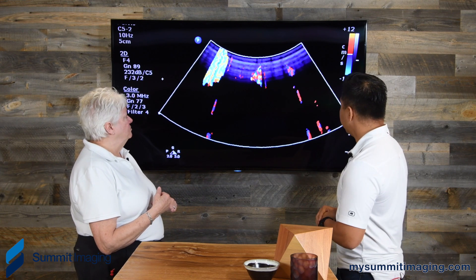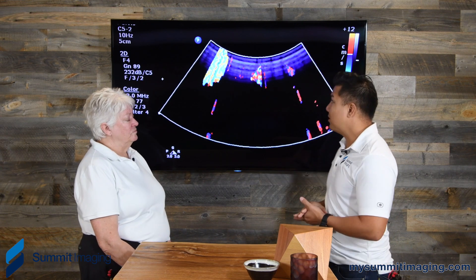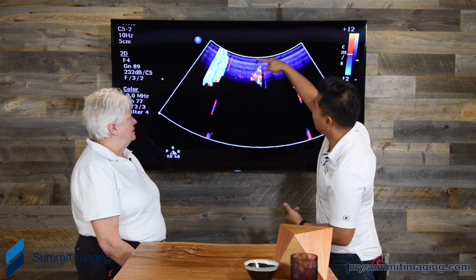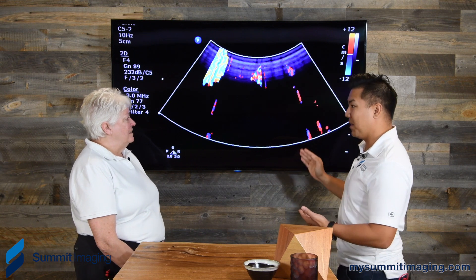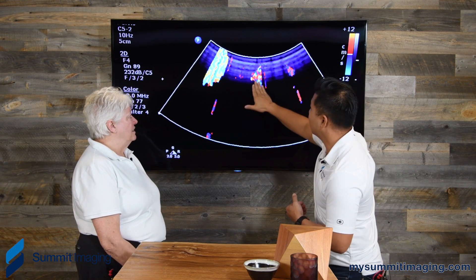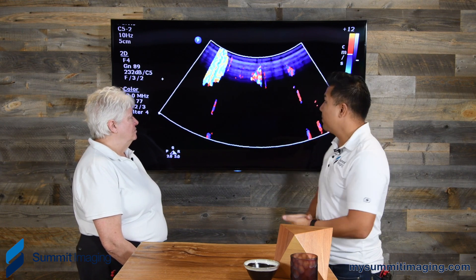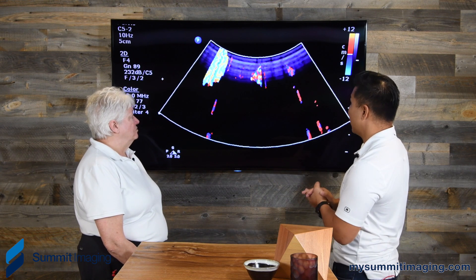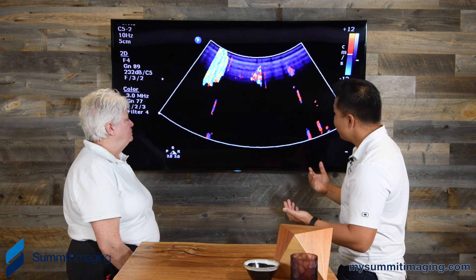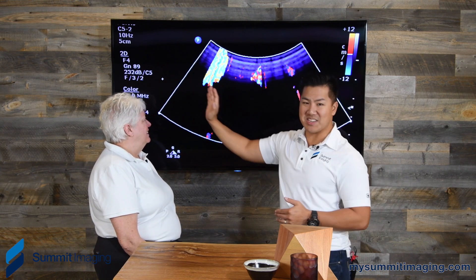Not impossible to repair, but this is significantly damaged. If you look at the technical pieces, you can see these color artifacts are an issue, and there's actually more damage than just the color here. You can see there are actual drops — and what that's telling us is that the drops not exhibiting color are actually circuits that are now open when they should be shorted the entire time. These noisy color artifacts are caused by circuits either intermittently and constantly touching, or the crystal is just sending the wrong information — it's off timing because it's been cracked somehow — and then it's just kind of speckling out. So it can happen in several areas. This probe has had a rough life, and you can see in the background there's actually more damage than just the obvious color noise we're seeing here.